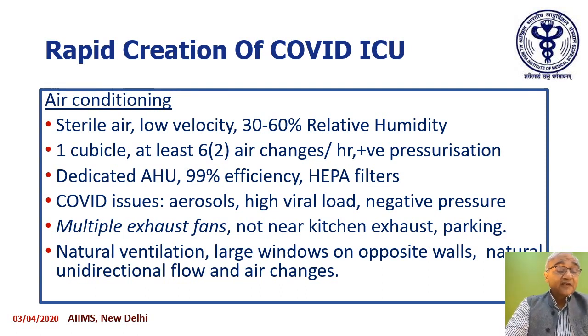This is at times difficult to achieve when making ICUs in an already functioning hospital. The easiest way is to dedicate or segregate AHUs, air handling units, to the area where an ICU is being planned. Special HEPA filters could also be fitted along with these dedicated AHU units, which increase the efficiency of sterilization of the atmosphere.